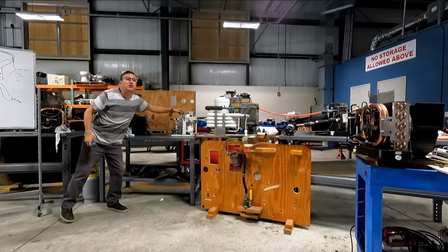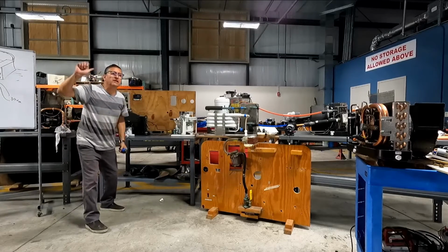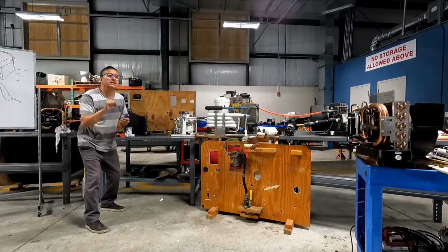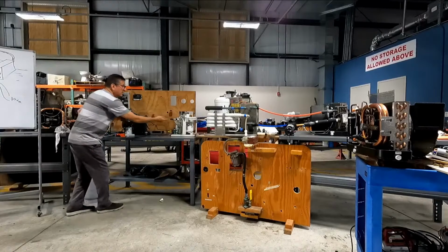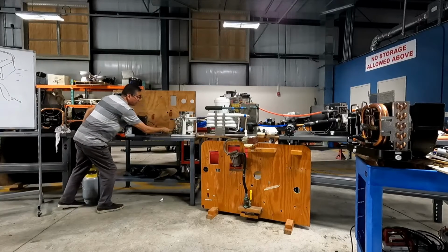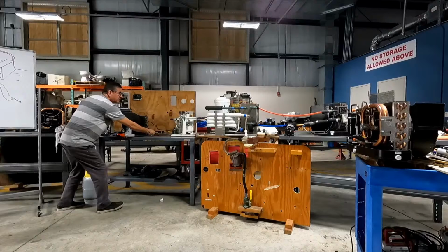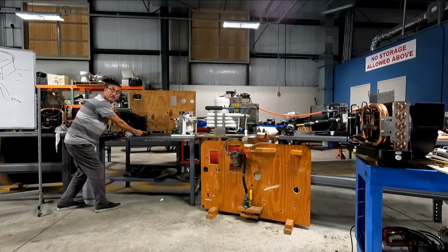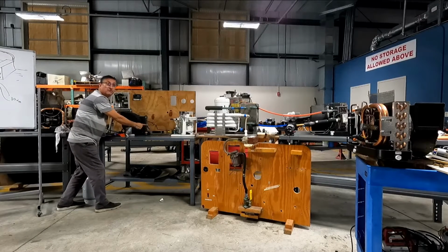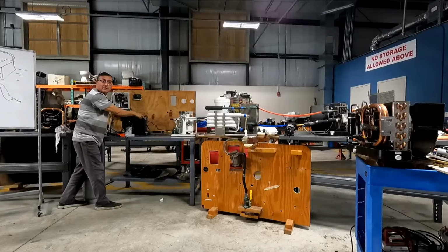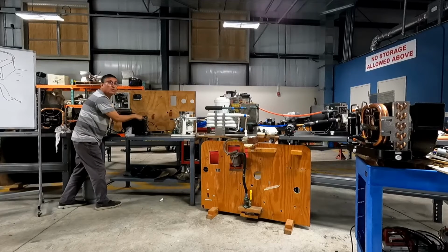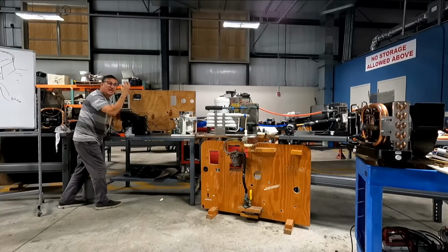The cycle starts in the compressor. The compressor receives the signal from the thermostat and starts to compress the refrigerant. In the discharge of the compressor, you have refrigerant at high pressure, high temperature. Yes or not? Yes. The refrigerant passes through the dryer filter and after that the capillary pipe. What happens to the refrigerant after the capillary pipe? It reduces temperature and reduces pressure.